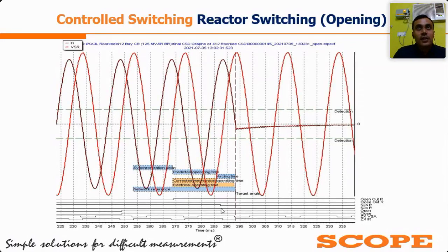So, my dear friends, I want to inform you that the CSD relay doesn't take part in protection. It only comes into the picture in manual operation. When we provide the command through TNC or BCU, only in that condition will CSD come into the picture, not in protection.